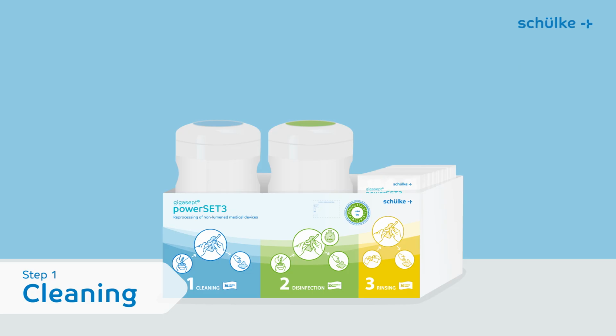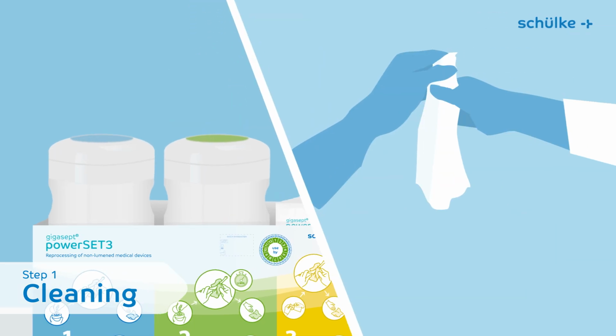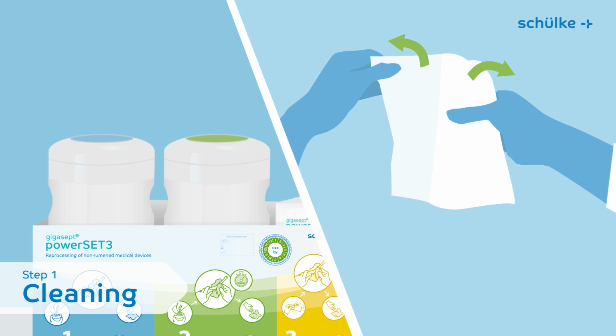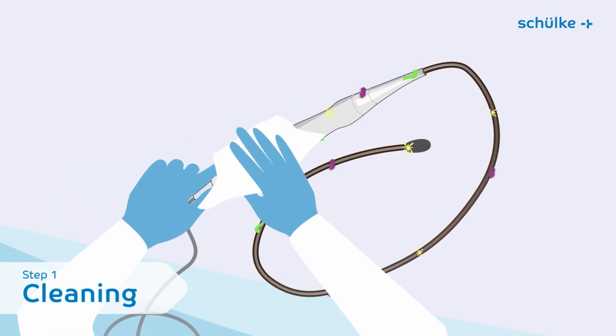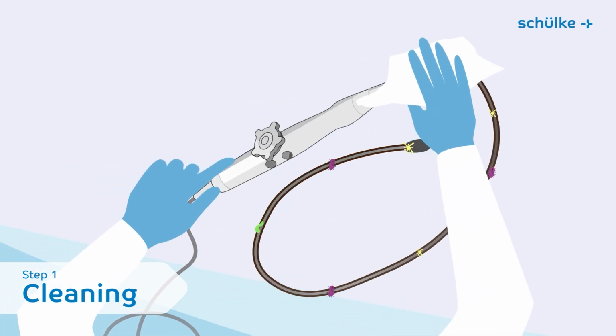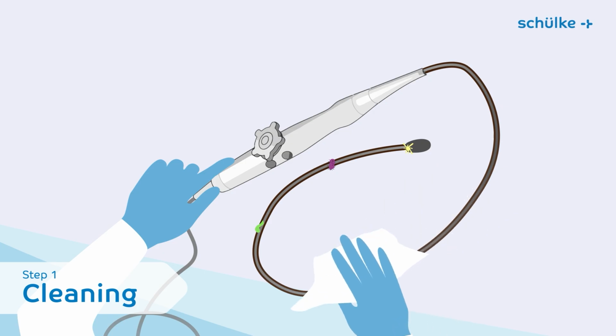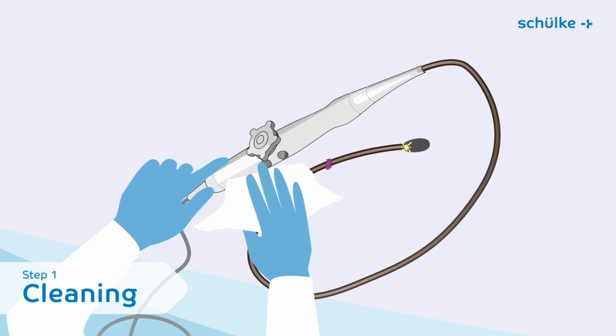The first step is cleaning. To do this, open the tub of gigasept powerSET3 cleaning wipes, take out one wipe and close the tub again. Unfold the wipe. Wipe the medical device thoroughly from proximal to distal until no more soiling is visible and all surfaces have a slight film of moisture.